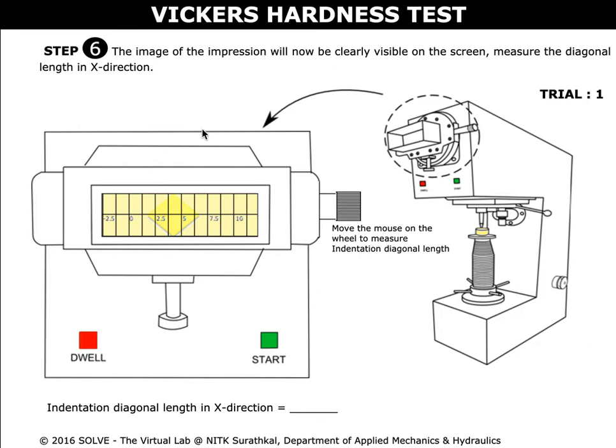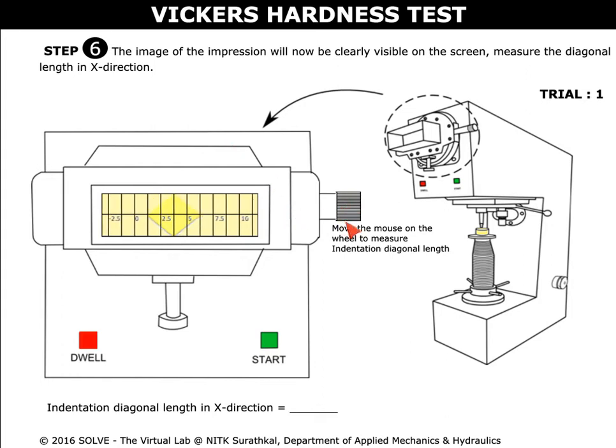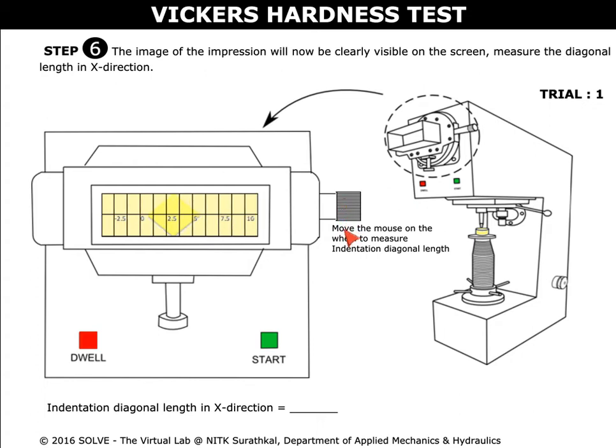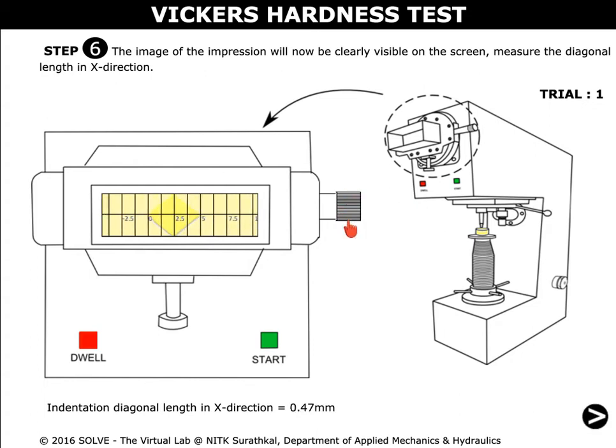Once the image of the impression is clearly visible, move the pointer here to measure the indentation diagonal length in the x-direction. The indentation diagonal length in the x-direction is now found.